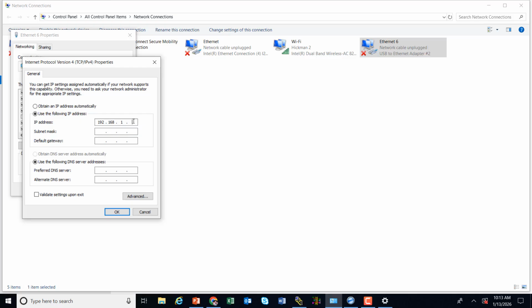It has to be different than that, and it has to be different than the controller, and it has to be different than any other device that we put on the network here. Over the course, we're going to have IP address conflicts because somebody didn't ask your partners what your number was, but I'm going to just make mine 25. So if I was 25, the controller can't be 25, the VFD can't be 25, the remote Ethernet can't be 25. Nobody can be 25 except me.